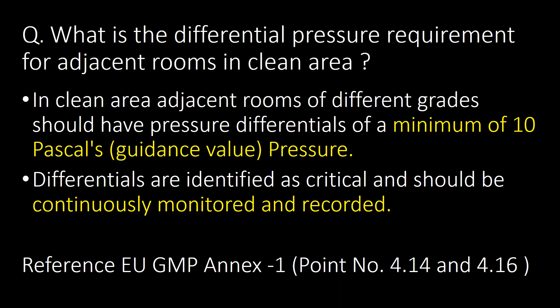What is the differential pressure requirement for adjacent rooms in a clean area? In a clean area, adjacent rooms of different grades should have pressure differentials of a minimum of 10 Pascals. Pressure differentials are identified as critical and should be continuously monitored and recorded. Reference: EU GMP Annex 1, Point No. 14 and 16.